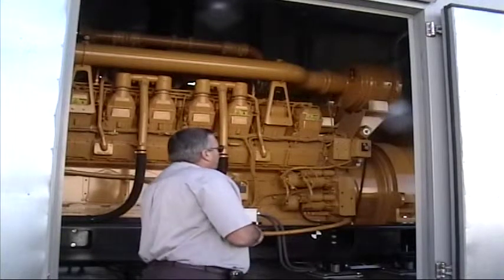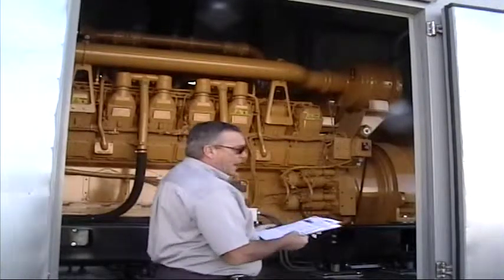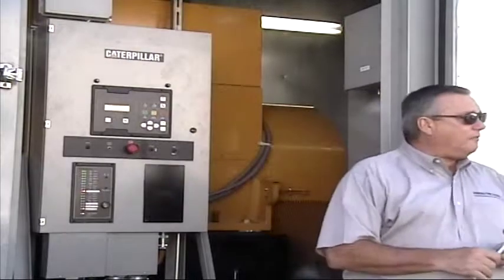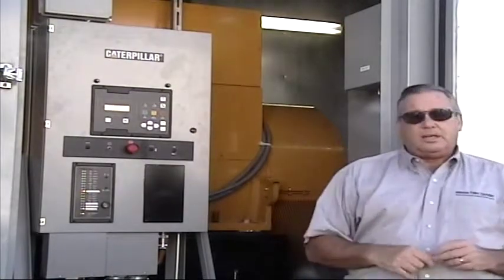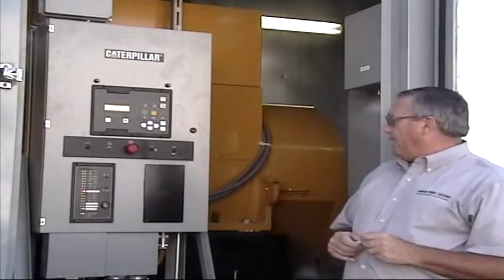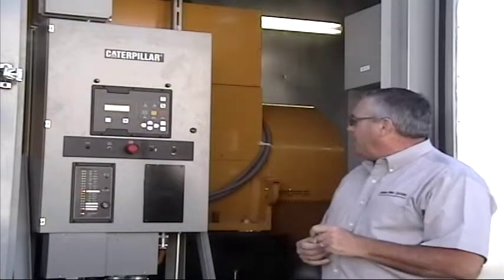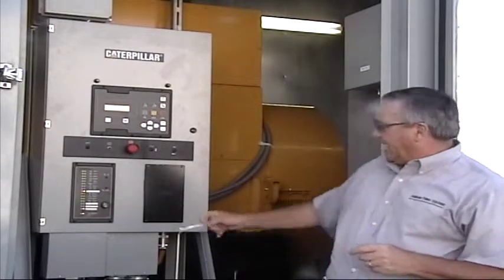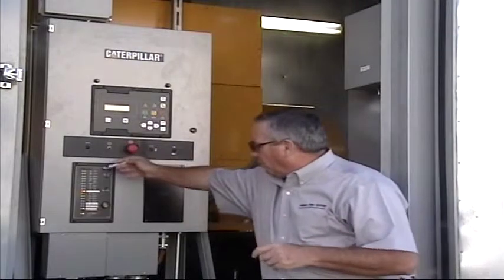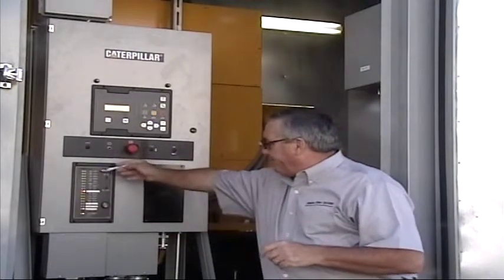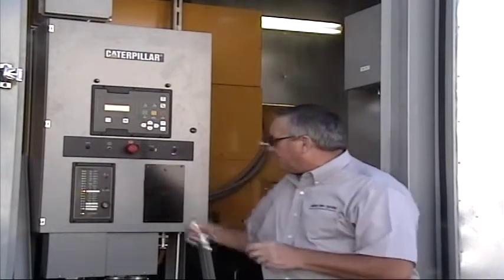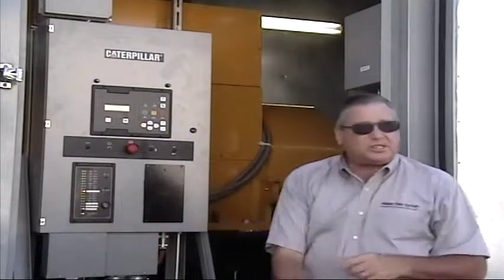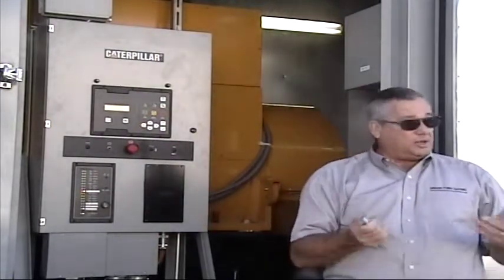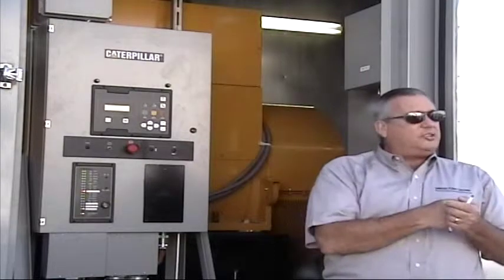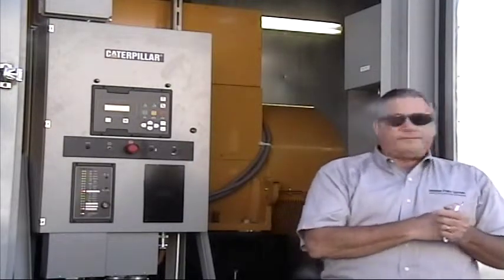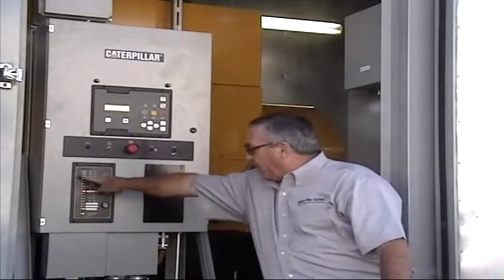Okay, we're going to move back to the control panel. On the control panel, the high fuel level is annunciated, which is going to burn down and get to the level where that light will go out. Basically, this is what we call a local remote annunciator, and I want to talk about some of these items here at the top. Emergency stop is what we call a shutdown. If that's engaged, the engine's not going to start, and you're going to get a red light over here.